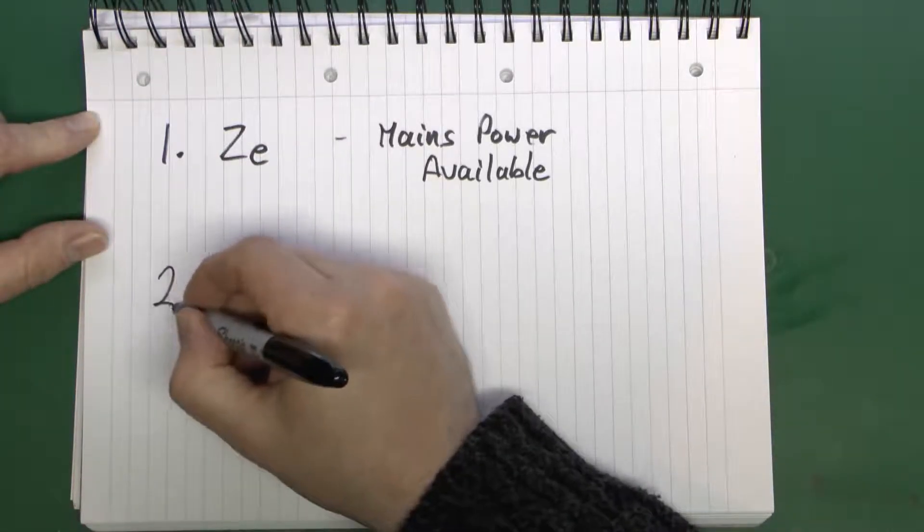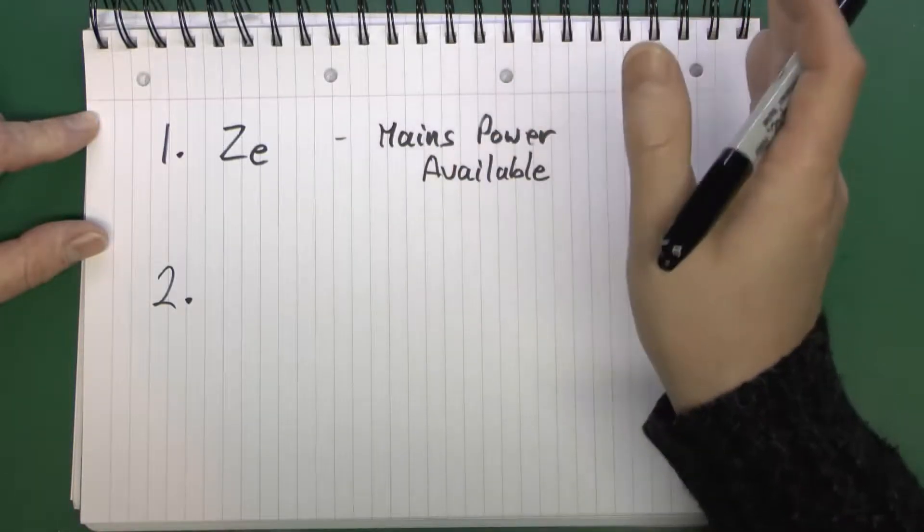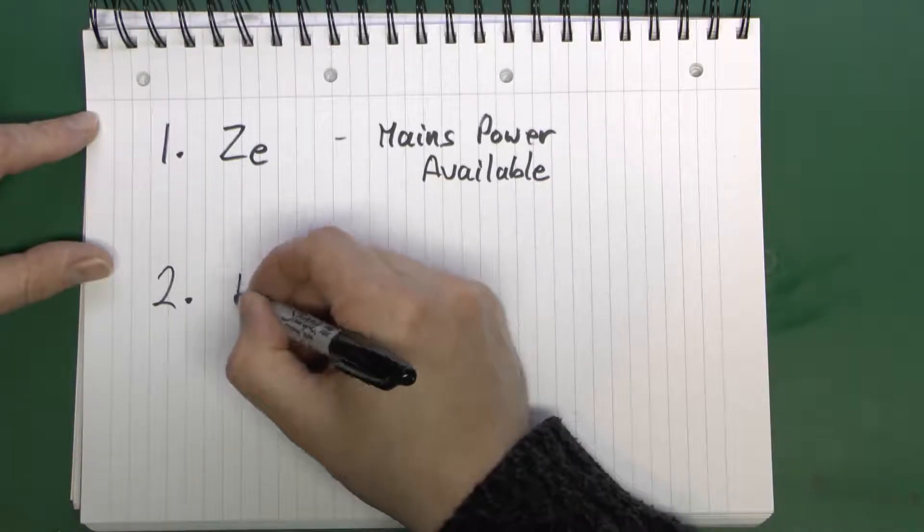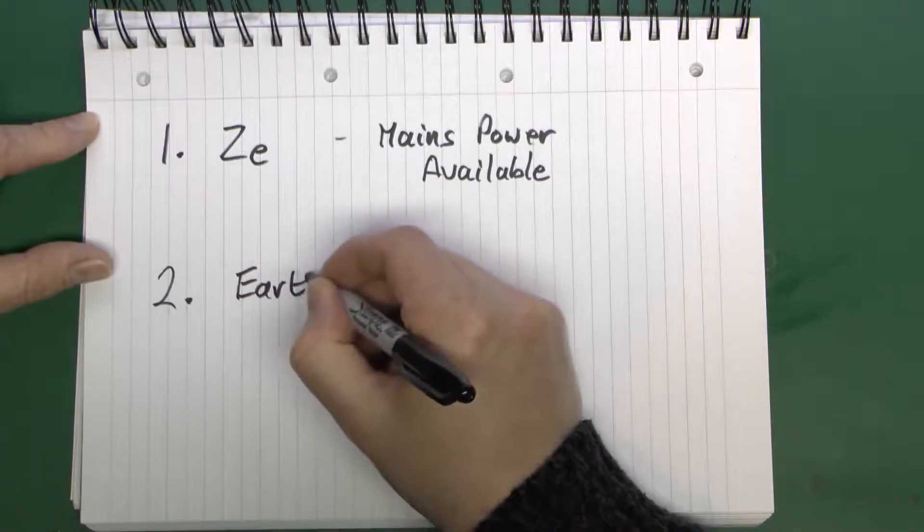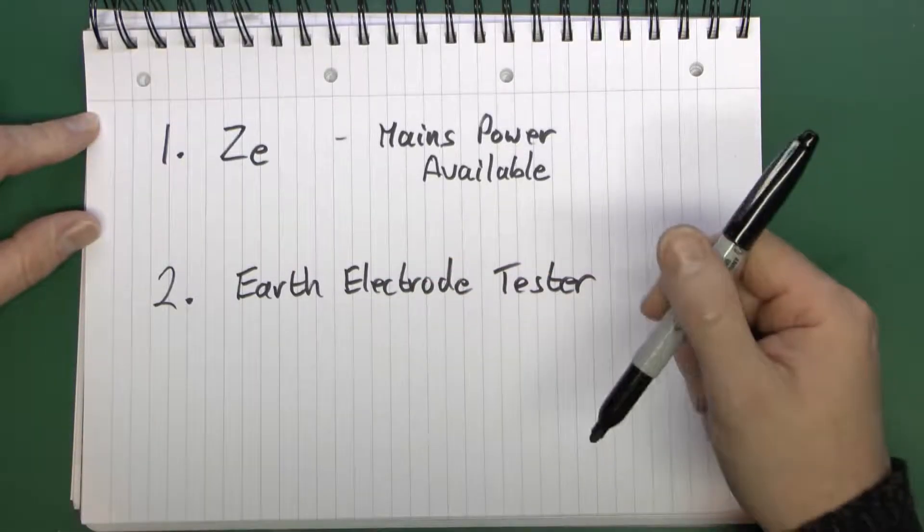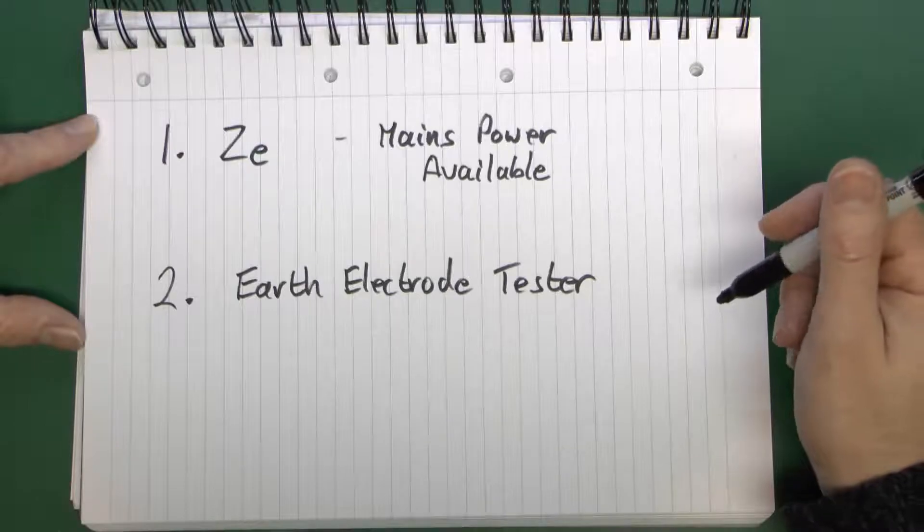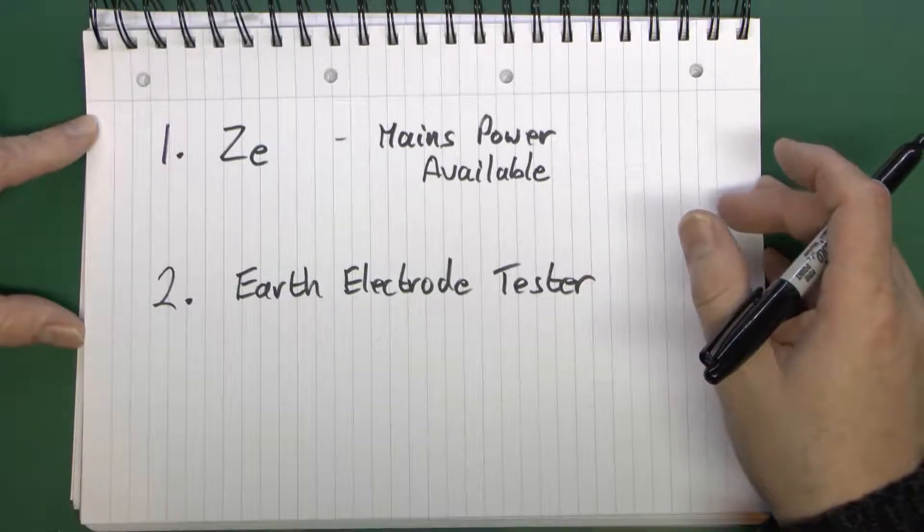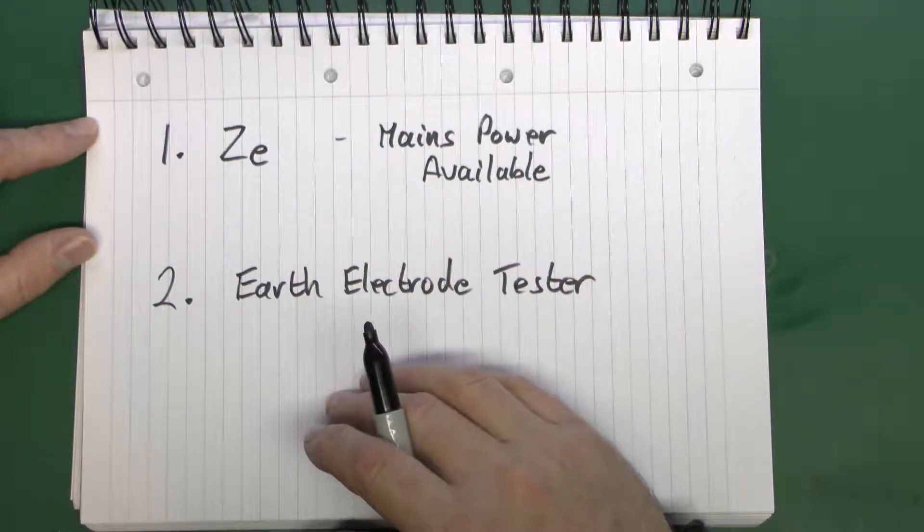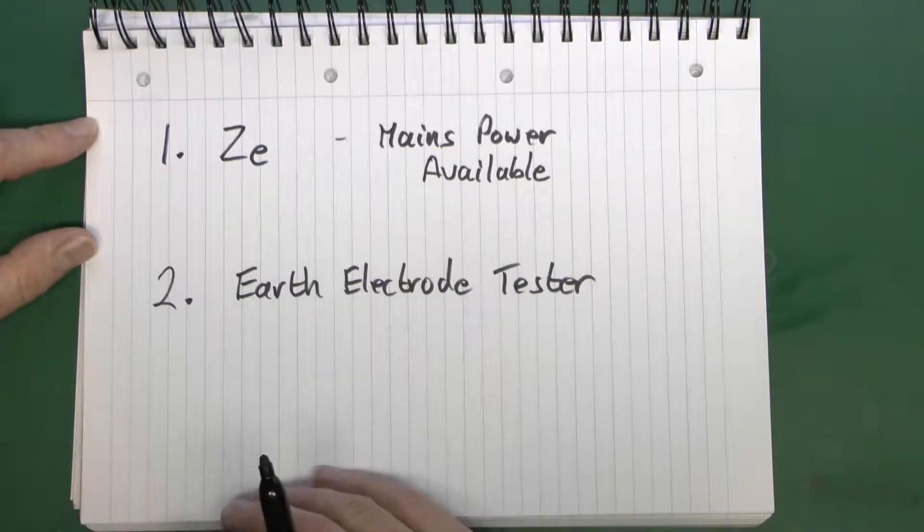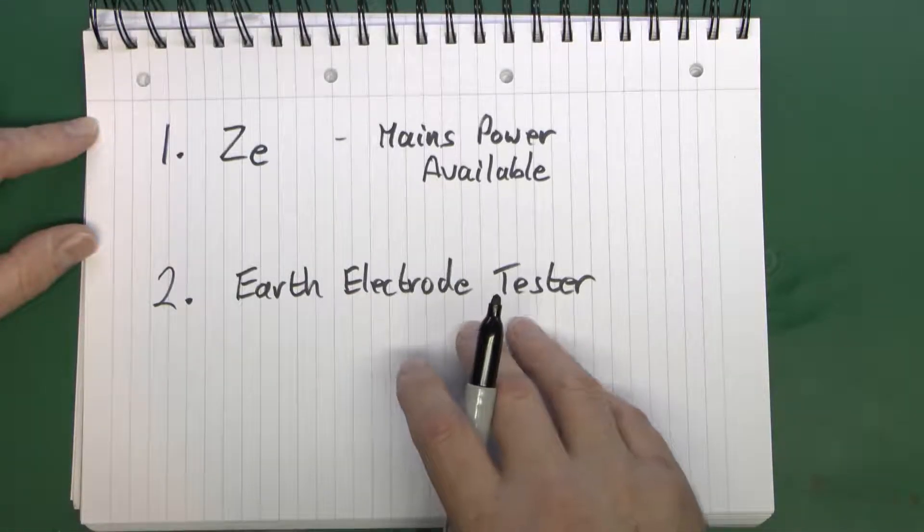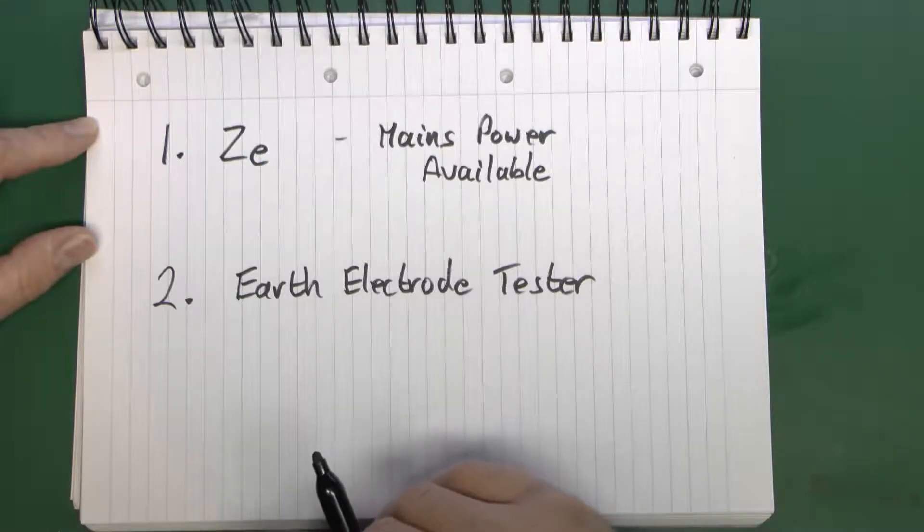In the case that power is not available, which certainly would be if there was a new installation and power hadn't been connected yet, the alternative method is to use an actual earth electrode tester. This does not require any mains power, it's battery operated, and can be done whether there's mains power available or not. This takes considerably longer and you do need the specific piece of test equipment to do it with.